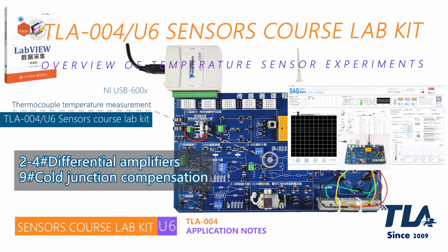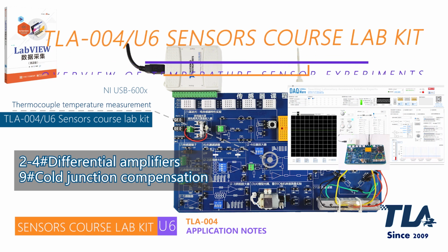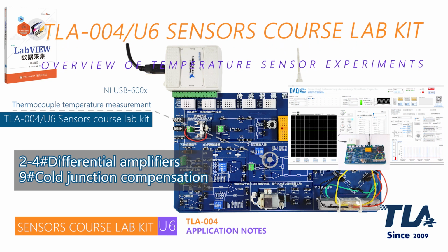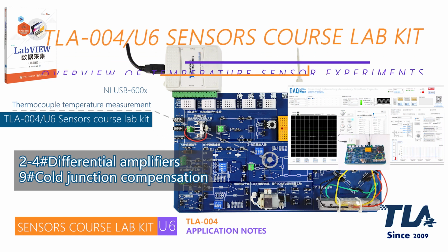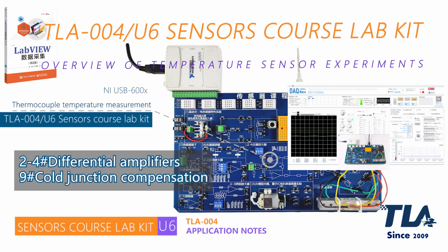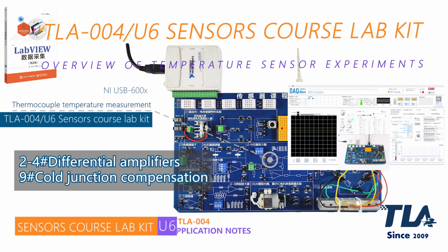with module 9. Module 2 to 4 is a differential amplifier module, which is a fully differential amplifier. 3 kinds of settable amplification factors are provided to meet the requirements of high-gain amplification of weak signals. In addition, the fully differential amplifier of module 2 to 4 is specially designed with a pre-filter, which can be seamlessly connected with the thermocouple temperature sensor to ensure reliable signal conditioning during thermocouple temperature measurement.